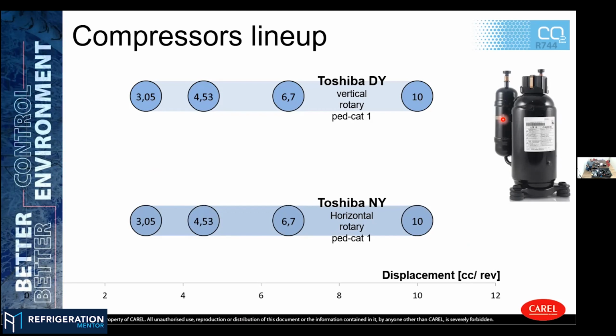Both of the models, this one and the other smaller one, have the suction accumulator tank. Okay, so in those, how does the oil get back to the compressor? Because I'm assuming, and I've seen inside different ones before, that you'll have a pipe up. So if any liquid does come back, like in any suction accumulator, you don't get the liquid back into the chambers. Is there a little hole in the pipe to meter back the oil, or how does that work?